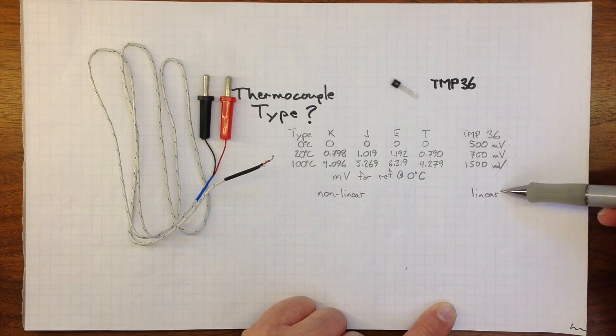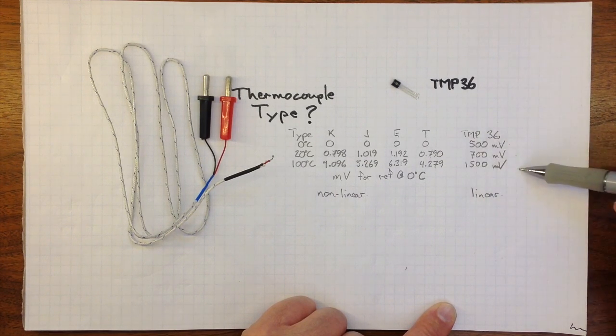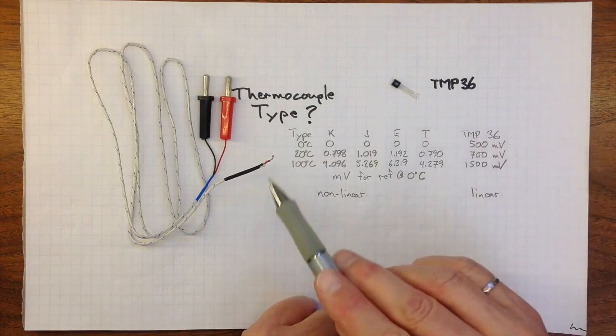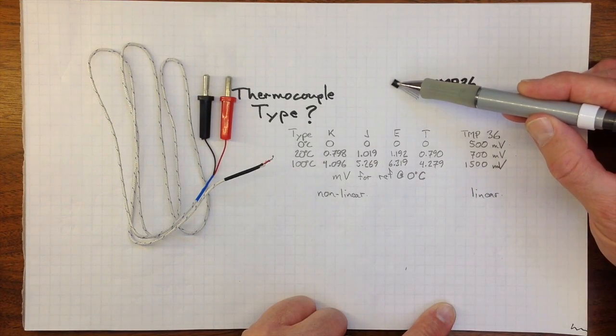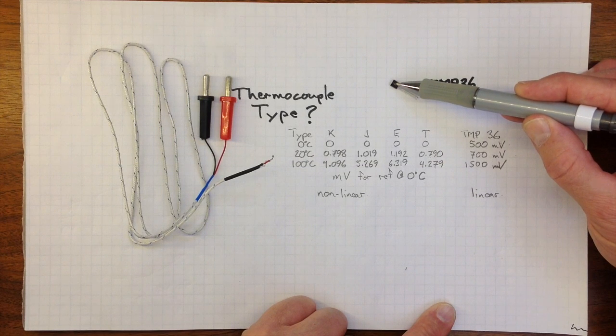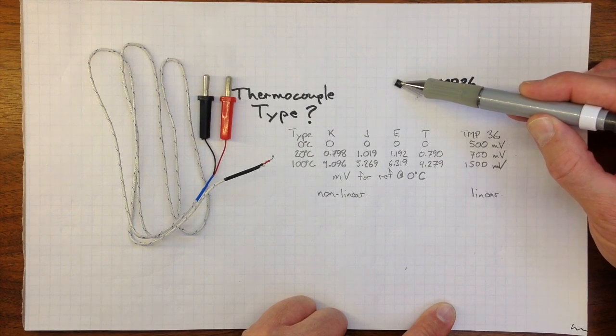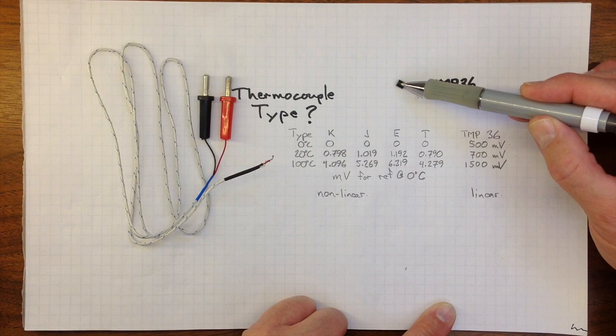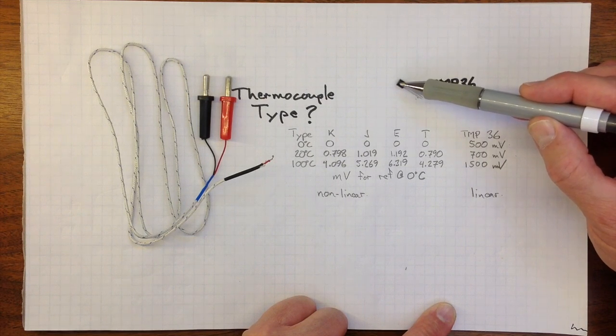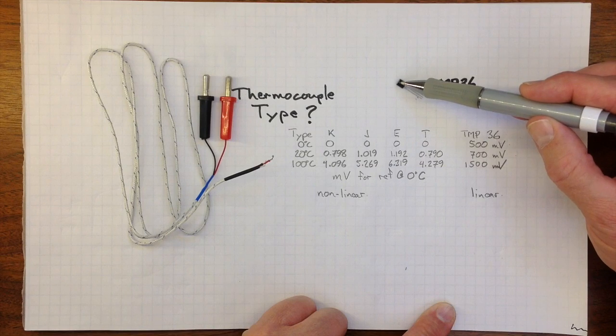So this one varies linearly, it's got a much higher voltage signal than the thermocouple, but because this black box is considerably bigger, it'll take considerably longer time for the black box and the sensor inside of it to get up to the same temperature as its surroundings.